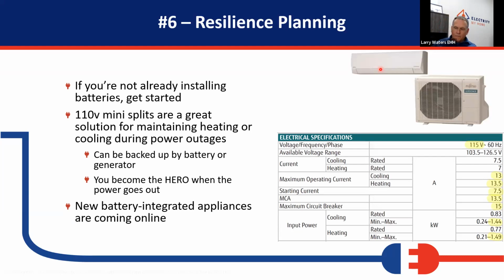So this is a nice solution for those situations. As you can see here, the input power on these things, when it's running at minimum output, is 0.24 kilowatts. That's 240 watts this thing is using. On a 10 kilowatt battery, that can go a long ways, obviously. It's 1.44 at max output. So this particular unit will give you a lot of cooling capacity. But when we use one of these, it cools or heats the room quickly, and then it slows way down to its slowest point. So somebody could cool a room down and keep it cool or keep it warm using a very low amount of energy off the batteries.